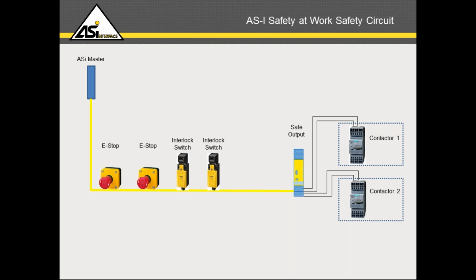As always, an ASi master is used, as shown up on the left here. It controls the communication on the network, and that ASi master can either sit in a PLC rack, like we're going to show in a second, or it can be a standalone device. There are a lot of devices from a lot of manufacturers out there. Safe input and output devices can also attach directly to the network, just like the standard devices. What makes these devices safe, as it were, is an ASi-safe chip and a special communication method that we'll go into in just a minute.